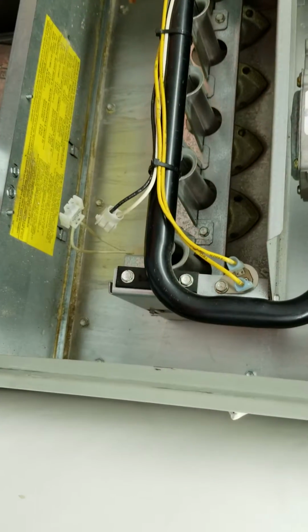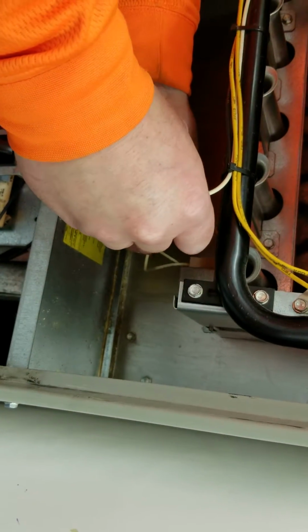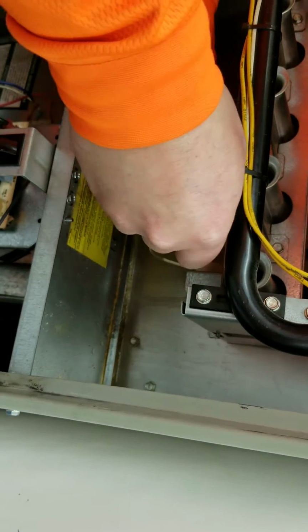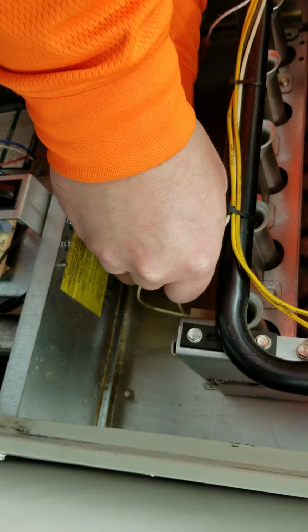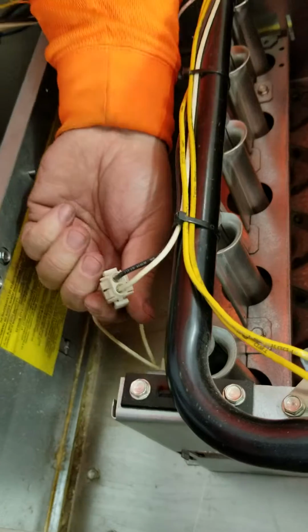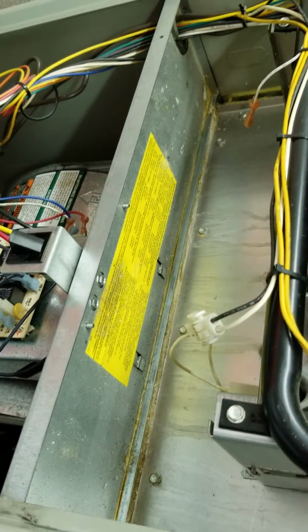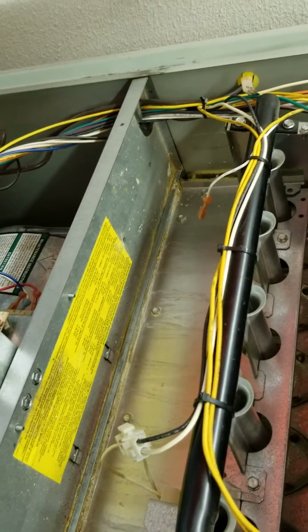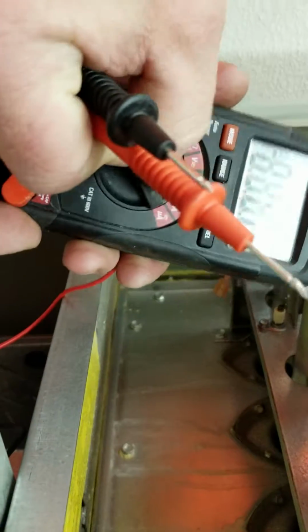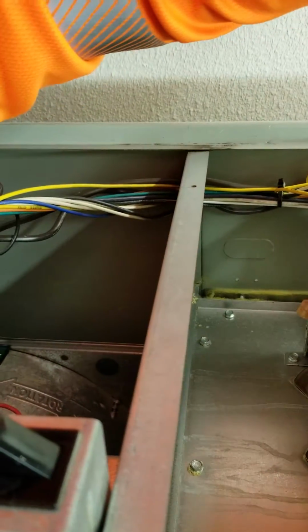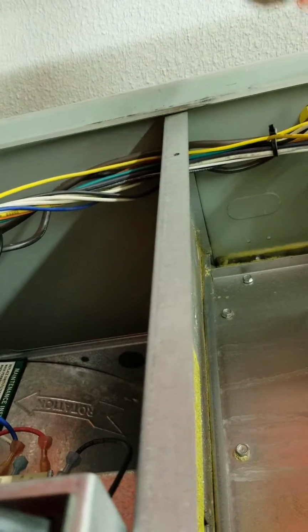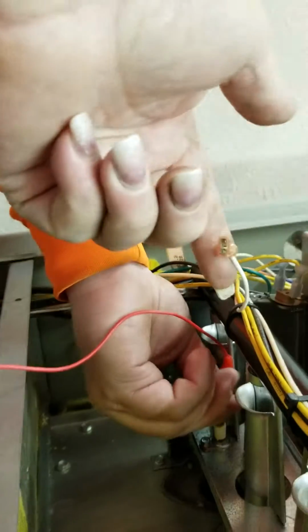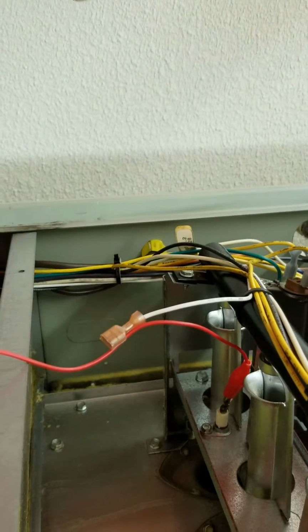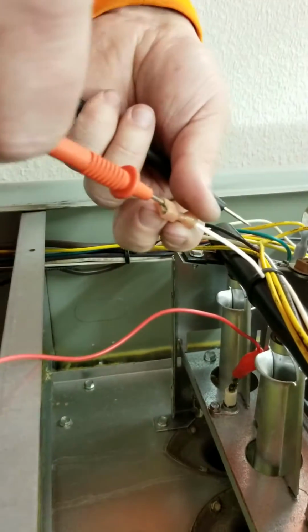Okay, now let's go ahead and plug in your hot surface igniter. Again, it's a one-way plug, so it only goes on one way. Yep, there you go. And then you're going to take your jumper lead and your microamp tool. In this case, go ahead. Okay, it will read 0 at this time. Okay, in this case, because it is a polarity sensitive device, the red lead is going to be where power is supplied, right there, to the flame sensor rod.